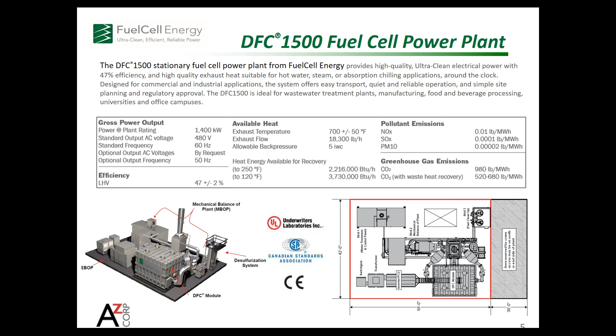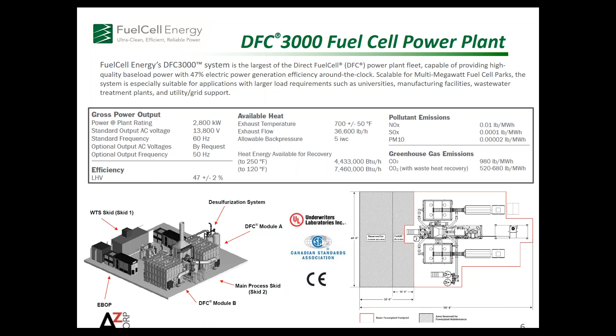Similarly, with our larger system, the 2.8 megawatt system, pretty much the specs are identical. The output is twice the size, and the footprint, I apologize that you have to squint just a little bit, is approximately 60 by 90 with a slightly larger area needed for replacement of fuel cell stacks at 5-year intervals. So the shaded area in the bird's eye view really is intended to signify where you roll the crane up and get those stack modules replaced every 5 years. Apart from that activity, the requirement is about 60 feet by 90 feet on the facility site.